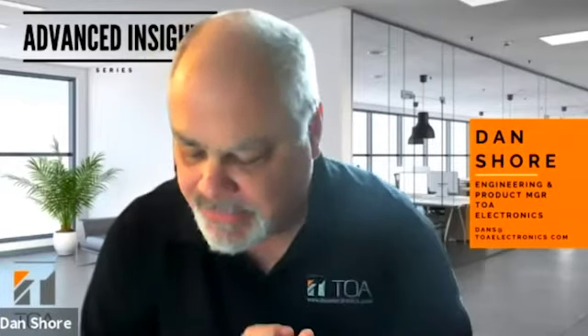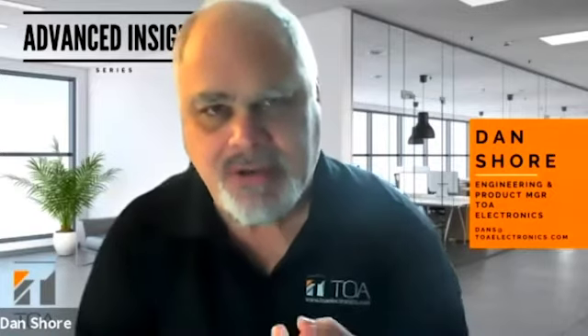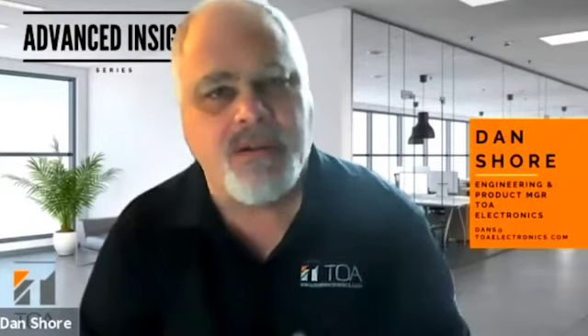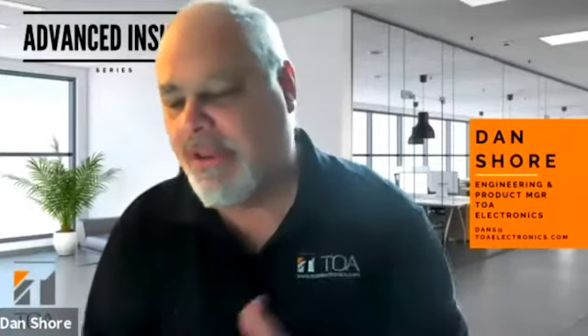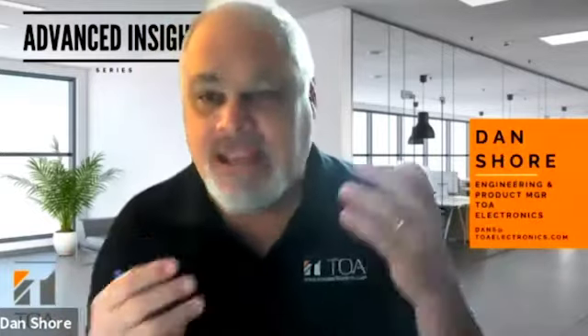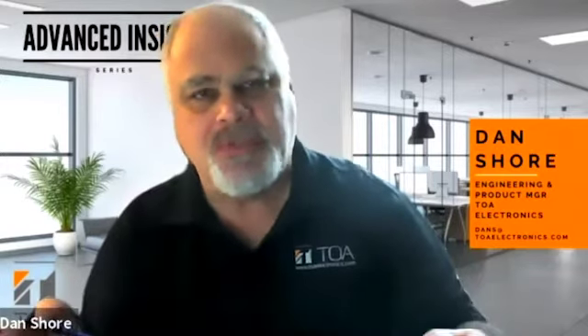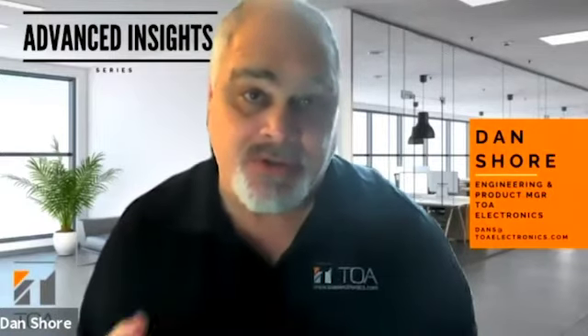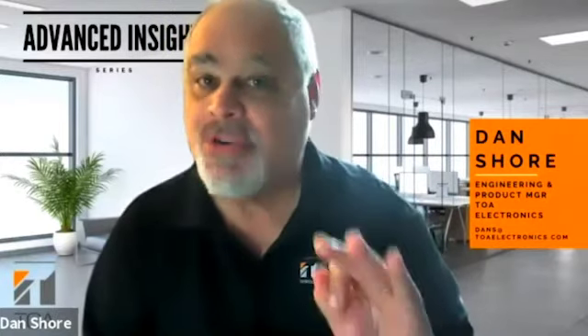There are a number of different ways that we can utilize this system. I've been in buildings where there are emergency communication systems, paging systems, fire alarm, and in a military installation, giant voice, there are four different sets of speakers in the building. With the TOA solution, the VM-3000, it's built to TOA's audio quality. TOA has been an audio manufacturer for almost 80 years now. So the full range, musical and speech quality on this is exceptional. So you can use it to replace all of the other systems while still meeting the requirements for NFPA 72, which is where you find the instructions and the code for mass notification systems, emergency communication systems.